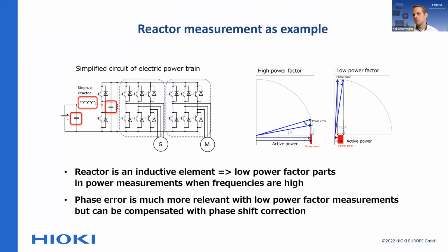And then if you look at the right graphic, you can see if you're dealing with a high power factor, then the phase error actually has a very, very little impact on the active power value that you measure. But if the power factor is very low and you're dealing very closely to the inductive side of this typical P and Q diagram, which means your phase angle is about 90 degrees or close to 90 degrees, then any kind of change in the phase error, and the phase error having an impact on the angle that you measure, has a big impact on the active power measurement that you do, and that will cause a measurement error and inaccuracies.